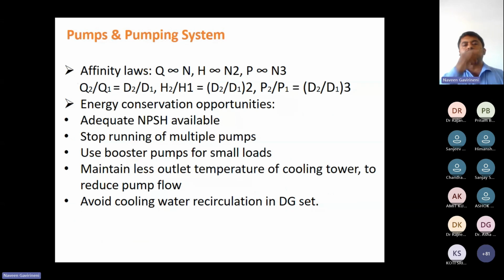As with fans, pumps also have affinity laws: Q, the flow, is proportional to speed; head is proportional to N squared, the speed squared; power is proportional to the cube of the speed. So these are the energy conservation opportunities. Adequate NPSH, net positive suction head.